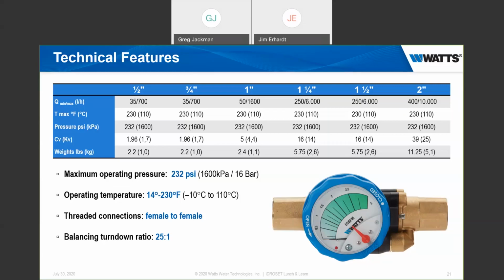You will see the maximum temperatures, etc. You'll see the CV values for each one. And in the engineering sheet, which we're going to show you here in a little bit, where you find that, you will also see the specified range for each valve. So we always size a valve based on its flow rate range, not on tapping size. So that's something important to keep in mind.